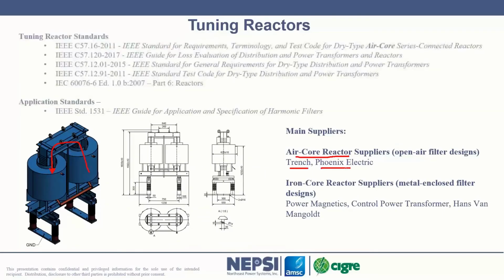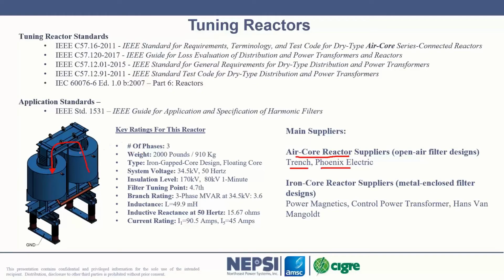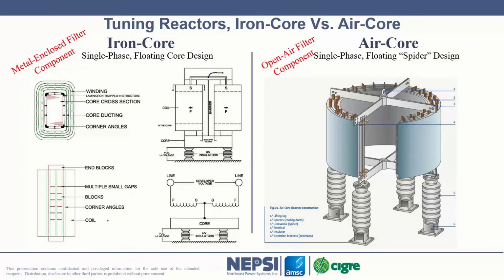So we've got some characteristics here I'm showing. Normally we're talking single phase reactors, or sometimes three-phase reactors. These iron core reactors can get quite heavy. They're using an iron core gap design in a floating core design, floating core because I have insulators here. And if you remember, the impedance of the reactor is small relative to the capacitor at the fundamental voltage. So the majority of the voltage drop in a harmonic filter is across the capacitor and not across the reactor. Therefore, putting the reactor up on insulators will help to improve the reliability of the design, because typically we might only have 500 volts across the reactor coil when operated at 50 or 60 hertz. So it's very low voltage.